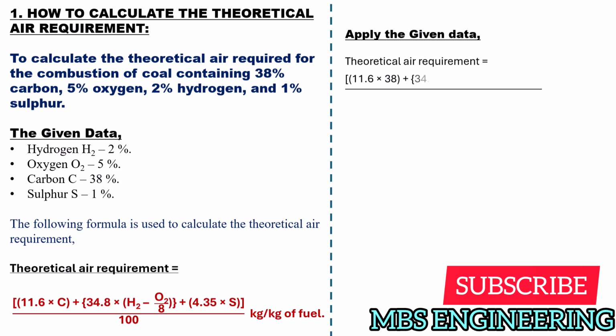Theoretical air requirement is equal to 11.6 times 38 plus 34.8 times (2 minus 5 divided by 8) plus 4.35 times 1, and then the obtained value is divided by 100. Its unit is measured in kilograms per kilogram of coal.